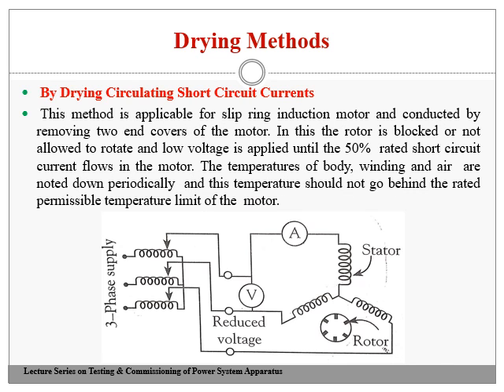Now, everyone probably knows this, as you might have conducted the experiment in the laboratories. This is drying of an induction motor with the short circuit current method, or what we normally call the blocked rotor test. What do you do here? Here we block the rotor and we apply reduced voltage until the short circuit current flows. When the short circuit current flows, heat gets developed because of the flow of current. Hence, the temperature of the winding goes on increasing, and hence it can remove the moisture content.